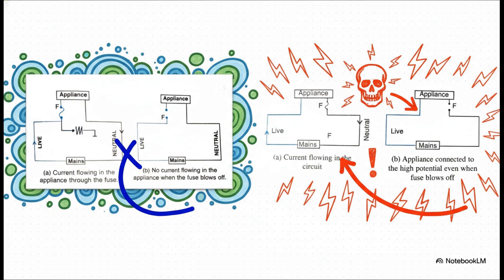Where you put that fuse is everything. It must go on the live wire. Take a look at the diagram on the left. When that fuse blows, the appliance is totally dead, completely cut off. But now look at the right. If the fuse is on the neutral wire, even when it blows, the appliance is still connected to that high-potential live wire, and that makes it incredibly dangerous to touch.